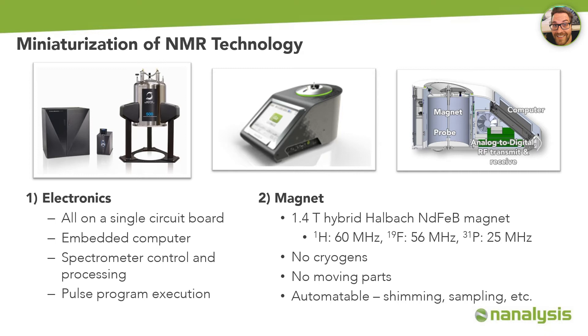The magnet is a 1.4 Tesla hybrid Halbach neodymium iron-boron magnet, which corresponds to 60 MHz in the proton channel. As the system is based on permanent magnet technology, no cryogens are required, and there are no moving parts which might get stuck and cause interruption of measurement operation. Automatable features like automated shimming allow the user to fully focus on the experiment.